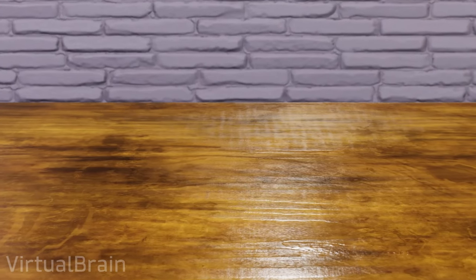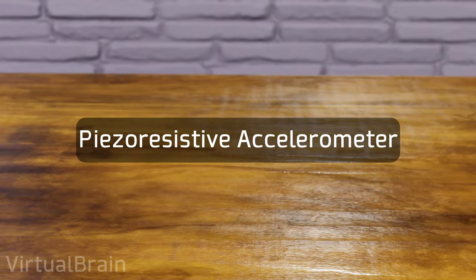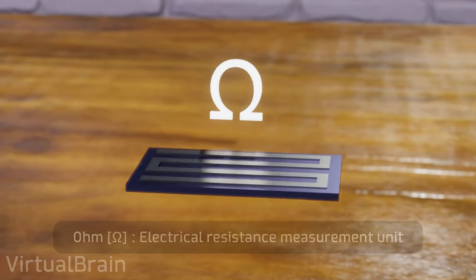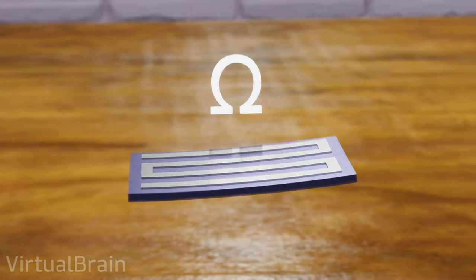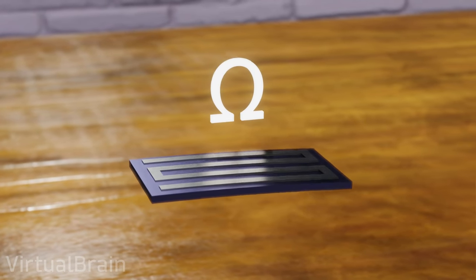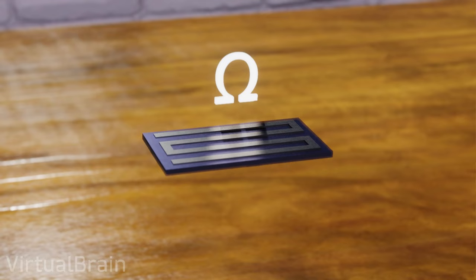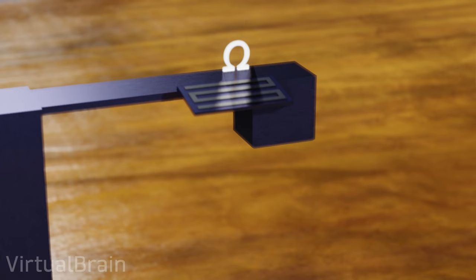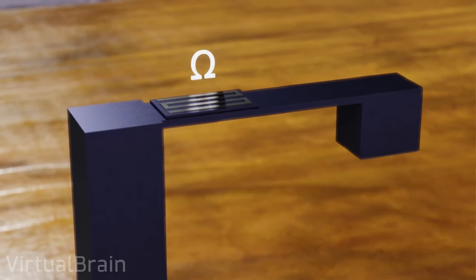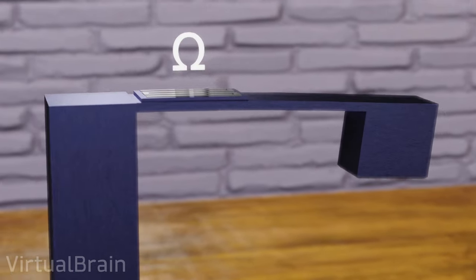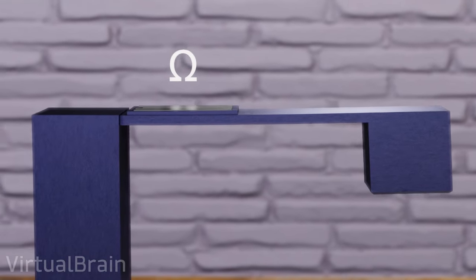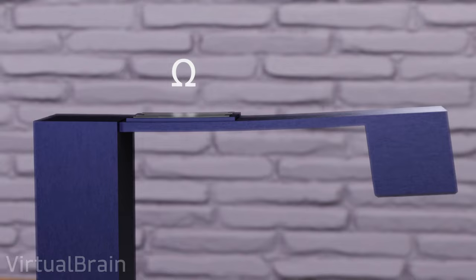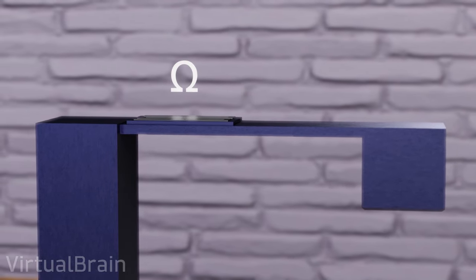The fourth type of accelerometer we will discuss is the piezoresistive accelerometer. These use, as the name implies, piezoresistive materials, which, when deformed, change their electrical resistance, that is to say, the ease or difficulty with which the electric current can pass through them. In one of the simplest versions of this type of accelerometer we could have a mass connected to a fixed place by means of a beam, positioning a piezo resistor on it. When an acceleration is applied to the system and the inertial force on the mass causes the beam to bend, the piezo resistor will compress or expand depending on the movement of the beam, allowing us to measure the new value of the electrical resistance and use that information to indirectly estimate the acceleration.